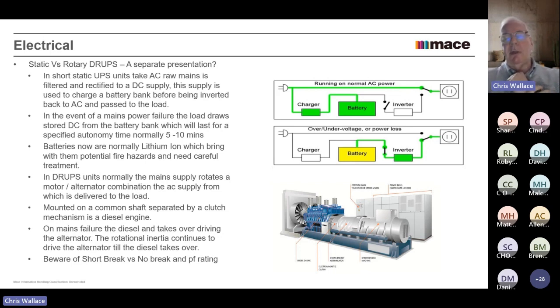If you contrast that with a rotary set, a rotary set is a great big motor generator block. Under normal situations, the AC power spins the motor generator up, and at the same time as it's spinning it up, you pull off the alternator side of it an AC supply which goes to the load. But what can happen is you have some sort of flywheel effect, and you have some other various magical black boxes which each of the vendors have their own version of. And basically, in the event of a failure, the inertia would carry it through for a certain amount of time.